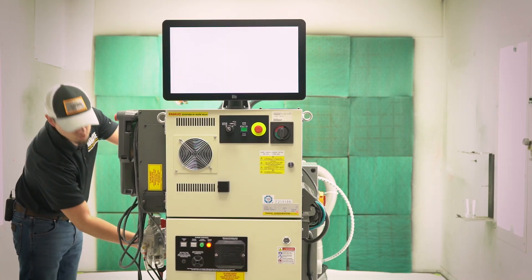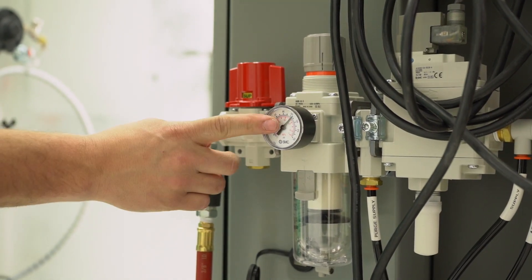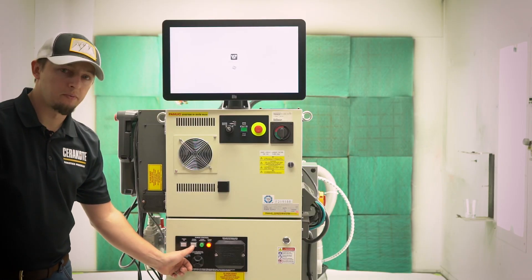We need 90 PSI at 12.5 CFM. Then we'll open up the main air regulator, and we'll be able to begin our purge enable process.